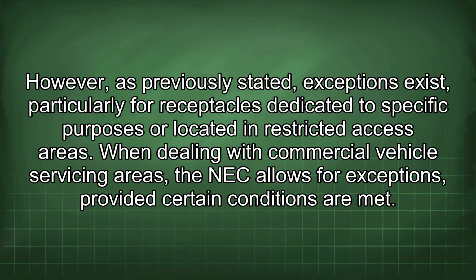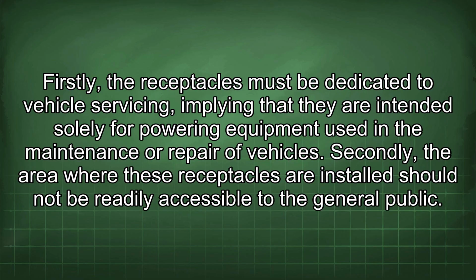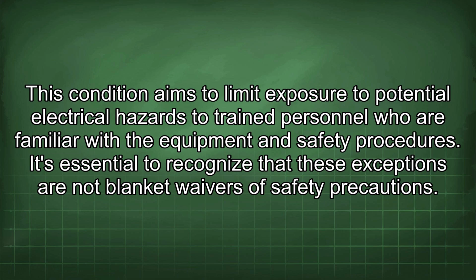When dealing with commercial vehicle servicing areas, the NEC allows for exceptions, provided certain conditions are met. Firstly, the receptacles must be dedicated to vehicle servicing, implying that they are intended solely for powering equipment used in the maintenance or repair of vehicles. Secondly, the area where these receptacles are installed should not be readily accessible to the general public.